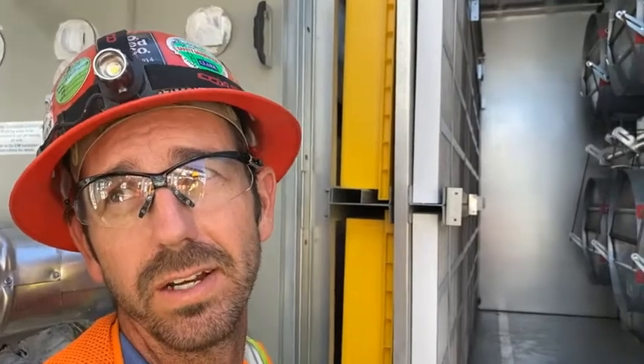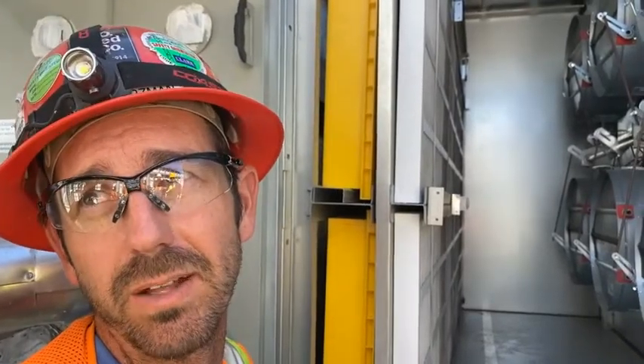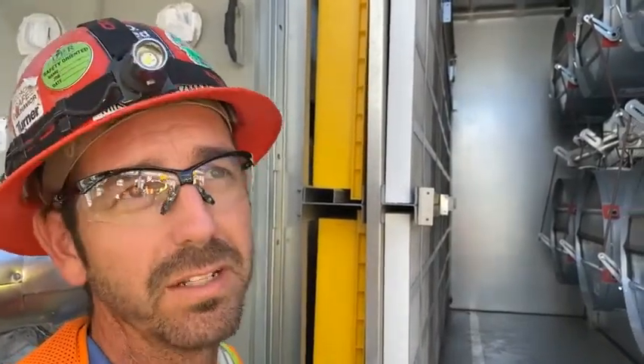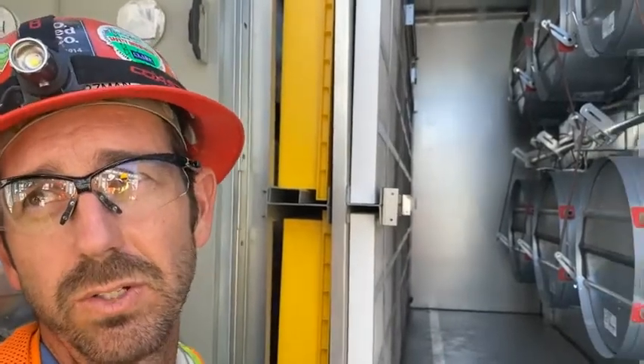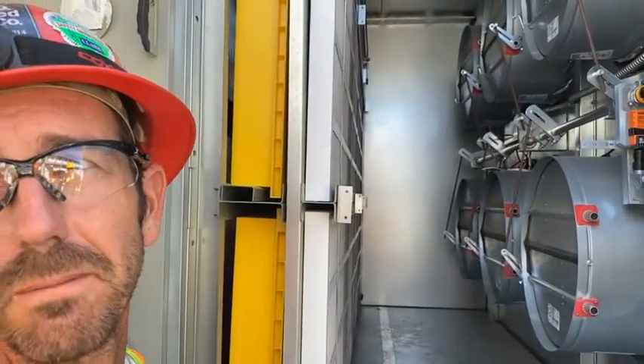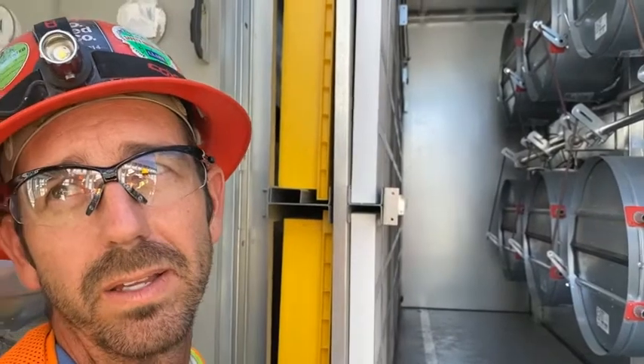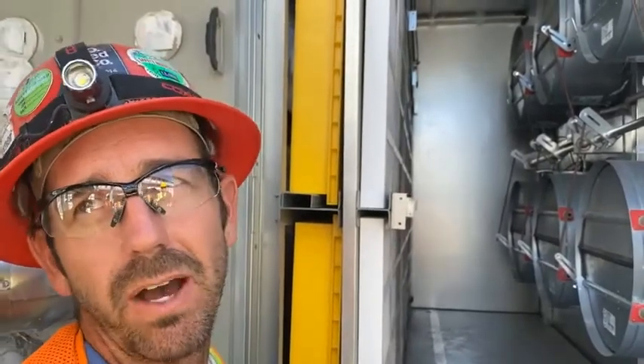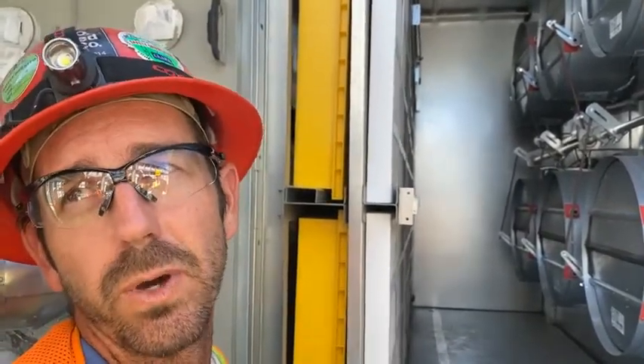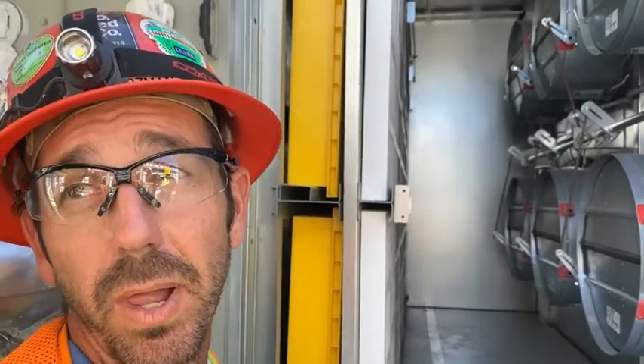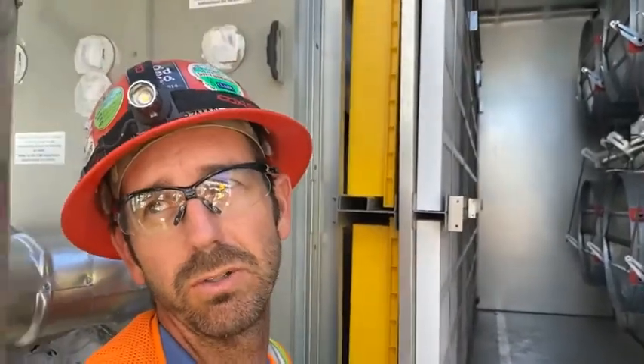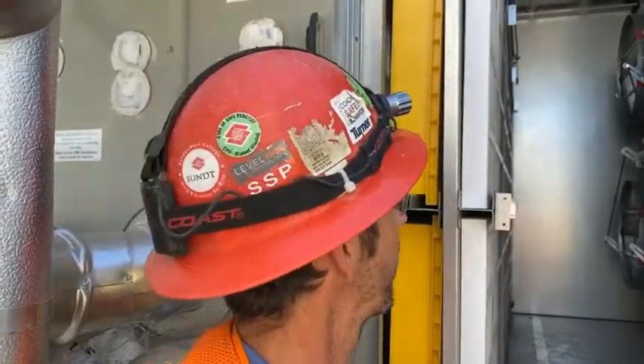From this air handler, right. And then there'll be a bunch of reheats downstairs that will reheat certain zones. So when you say zones, we just want to make sure we're on the same page. We have hot and cold piping. In case the temperature ever drops really low out here, we always want to be delivering a certain supply air temperature. So if it's too low, we can use the hot water to boost it back up. I would say about 98% of the time we're going to be cooling the air, right? It's pretty much warm out here all the time, okay?